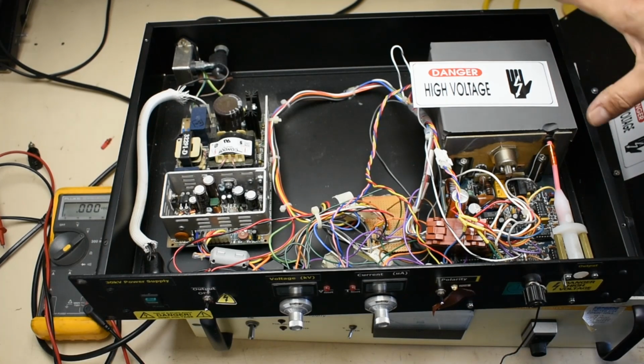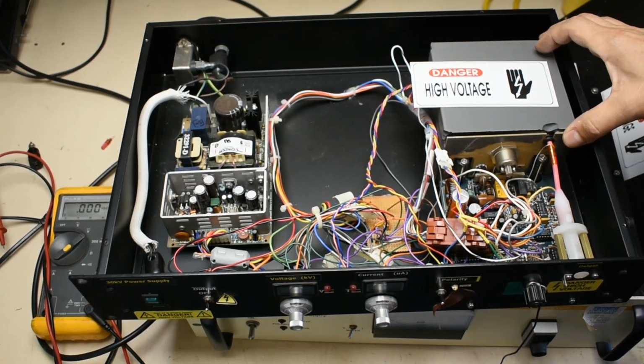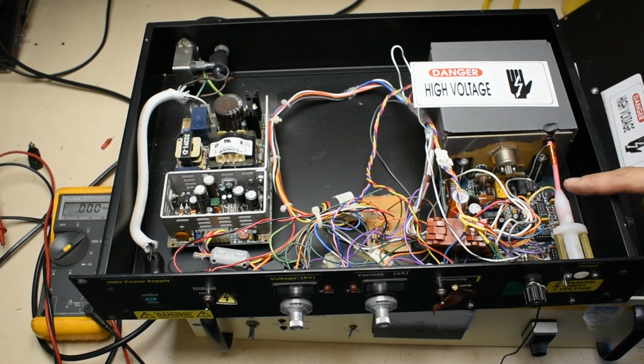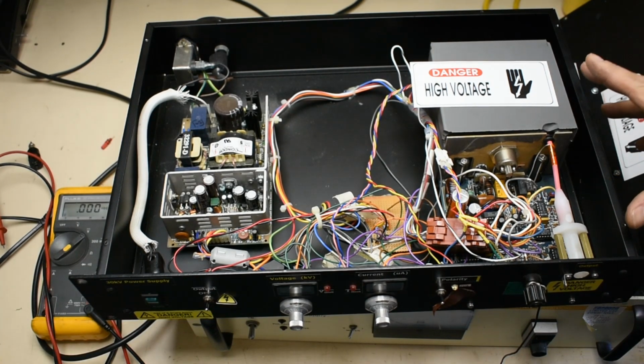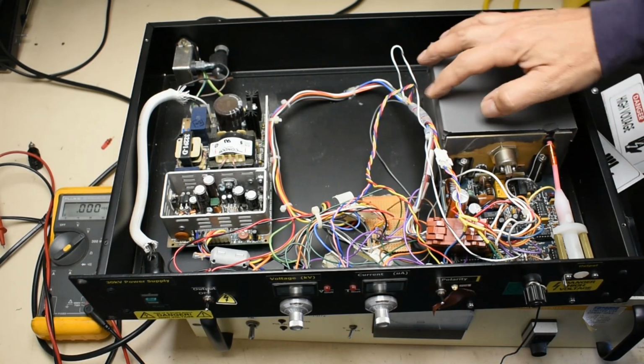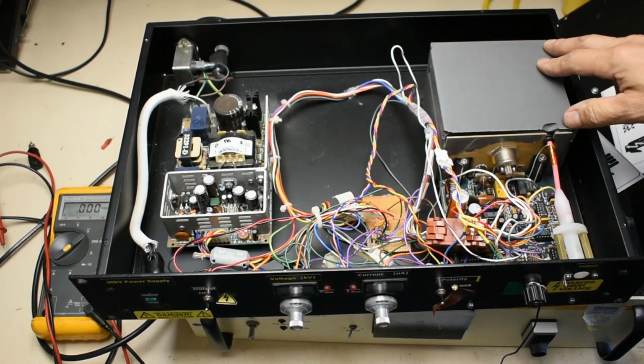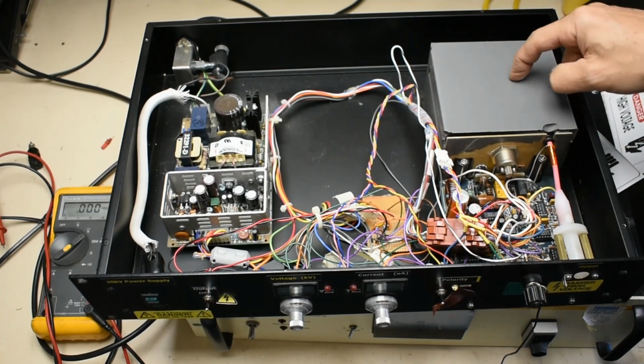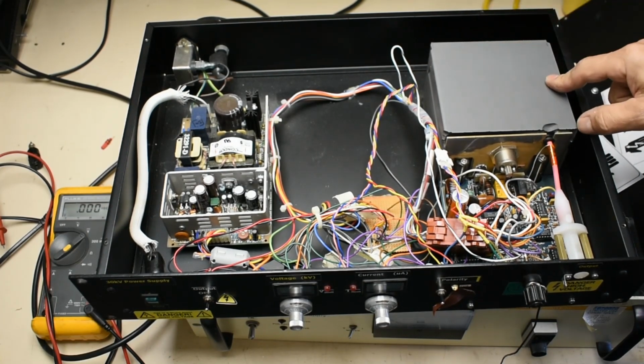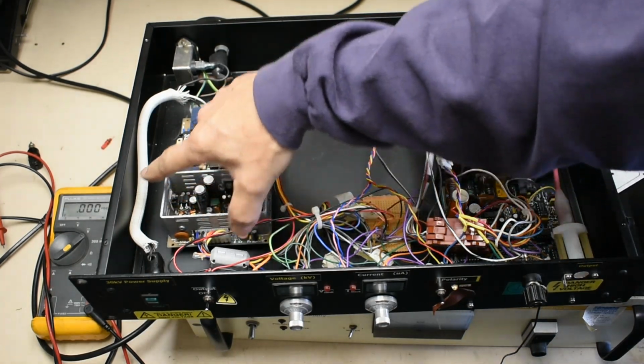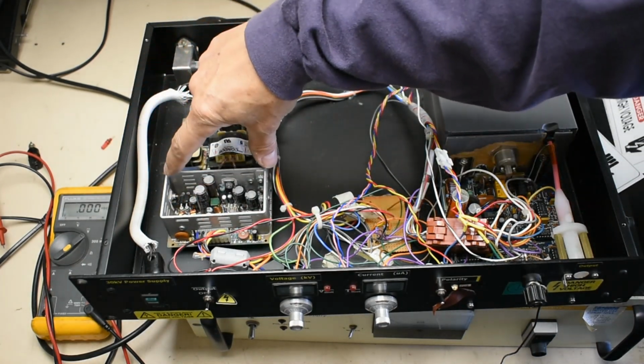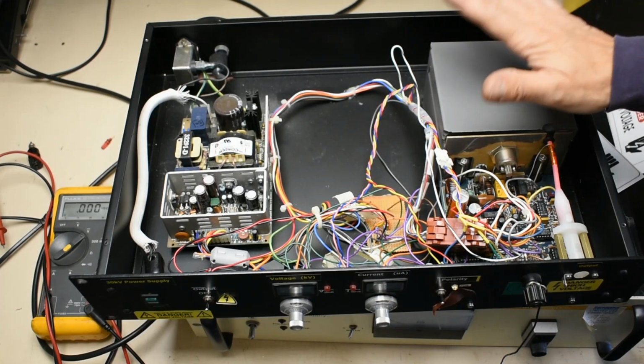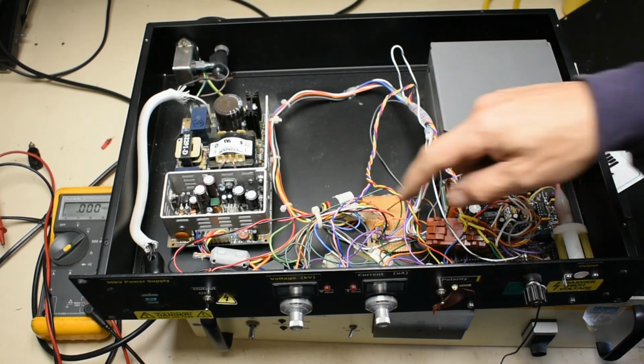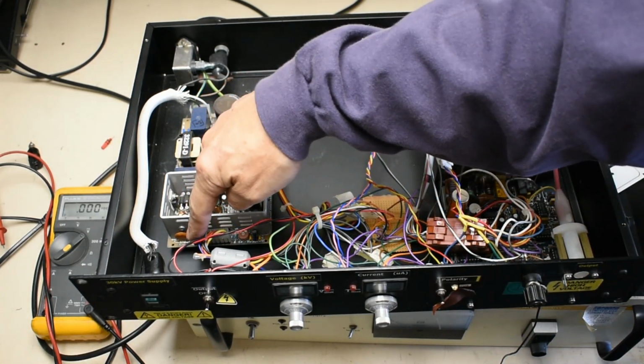It's based around this Spellman module, which generates plus or minus 30 kV, but only at 500 microamps, so quite a low current. You can see this part is where the high voltage unit is totally potted into silicone rubber. This part is just your switch mode power supply for 24 volts DC, which drives the supply here. There's also 5 volts and 15 volts available here.